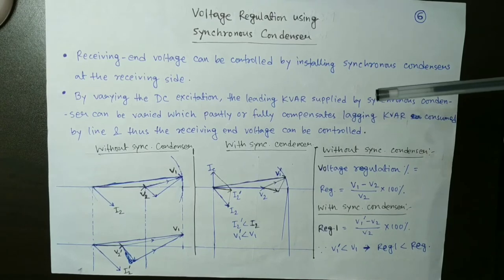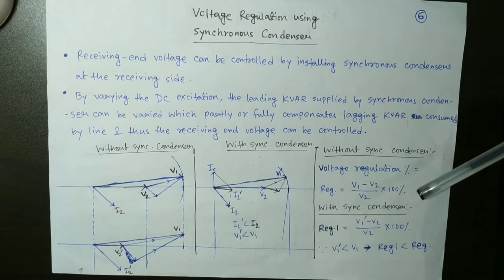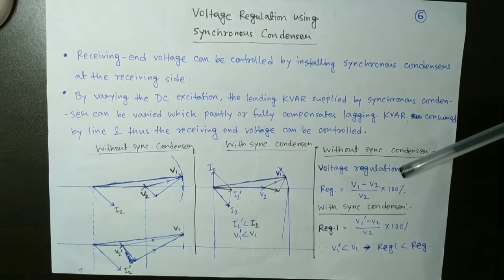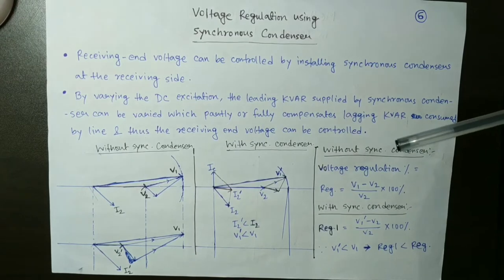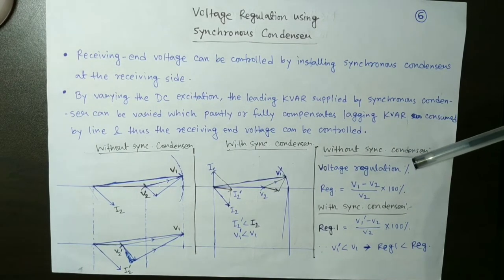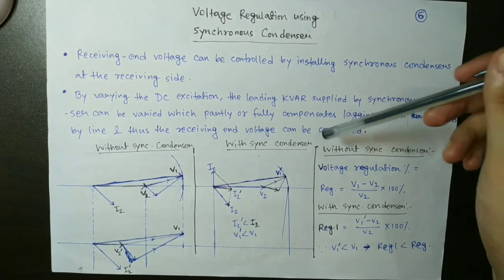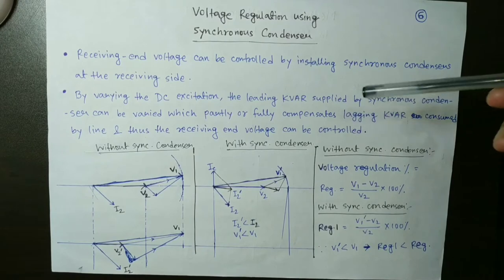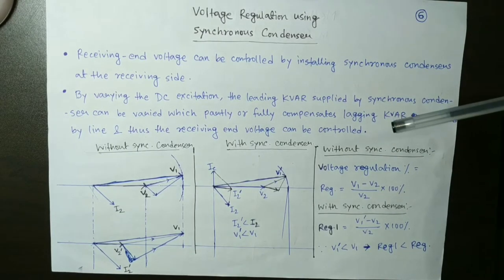By varying the DC excitation you can control your leading reactive power, which can either partly or fully compensate the lagging reactive power consumed by the transmission line. Hence the voltage drop in the line can be decreased, which means the current drawn by the load will also be reduced, and the receiving end voltage can be controlled and improved.